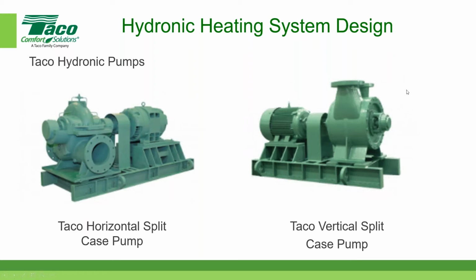Typical. Yeah, so the one on the left is a horizontal split case. The one on the right is a vertical split case. You can see the bolts around the perimeter here. And so if I'm drawing a vertical line, that entire front of the pump comes off in this direction. That allows you to service the pump.